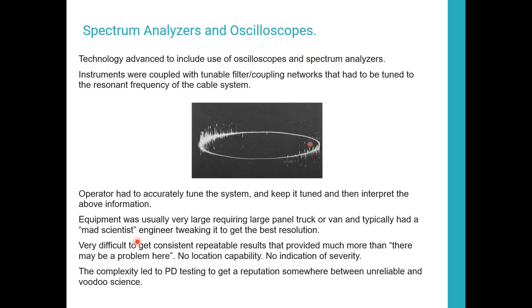So it was an extremely, extremely specialized field that had very specialized equipment. And in all honesty, it ended up with a result that there may be a problem here, there may not be. And it did find problems, but it also led to a lot of false positives. And partial discharge testing during this period of time got a bad rap because it was so specialized, and you could run a test three times and you may get three different results. So it was very inconsistent and very difficult. It took some extreme experience and knowledge to get a possible response out of it.